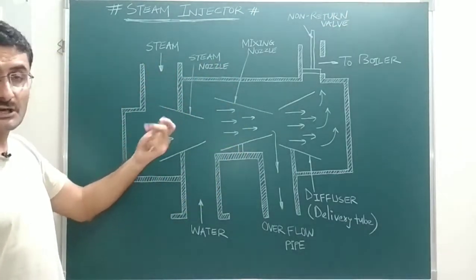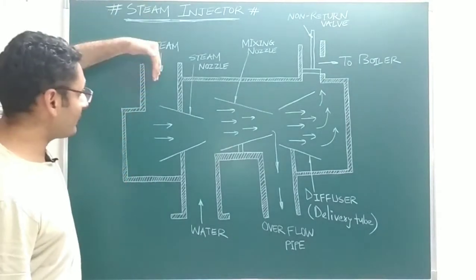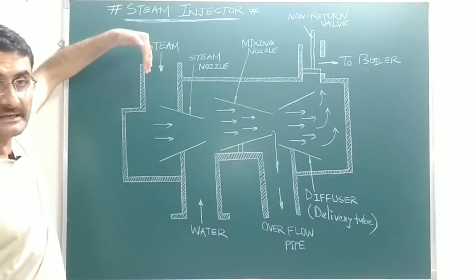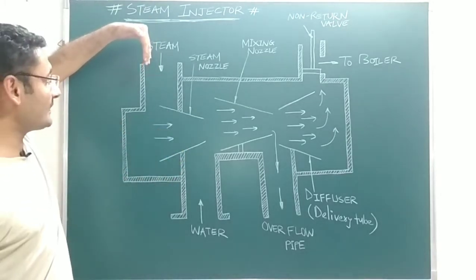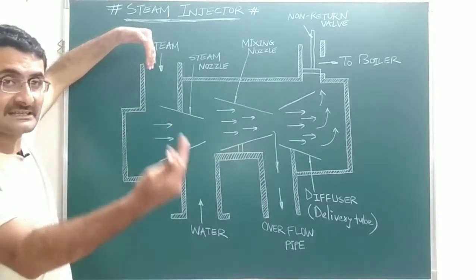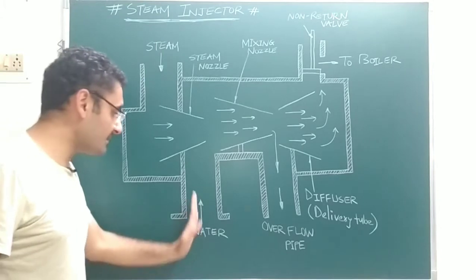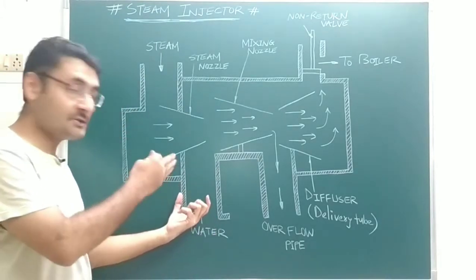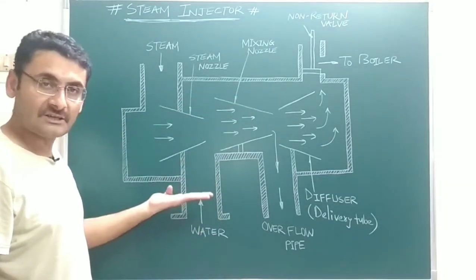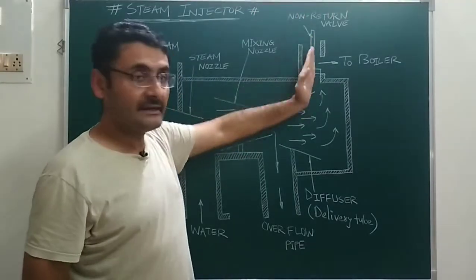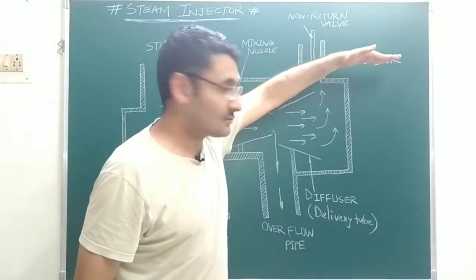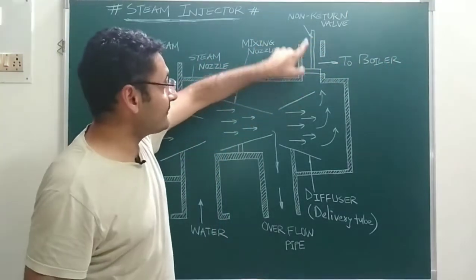Now, the construction: the steam injector has two inlets. Through the first inlet, exhaust steam or live steam from the boiler enters. Through the second inlet, water is supplied — water that needs to be fed into the boiler at increased pressure. There is one outlet connected to the boiler to supply high-pressurized water.